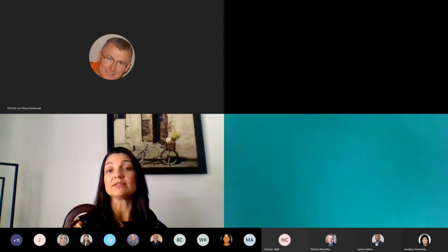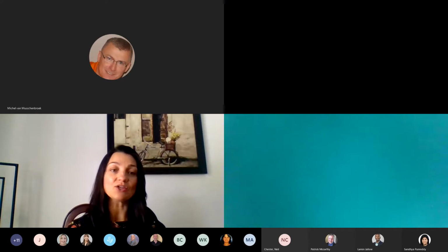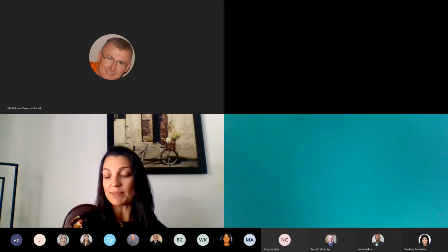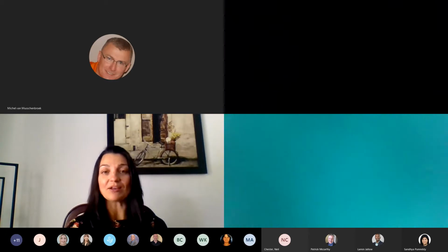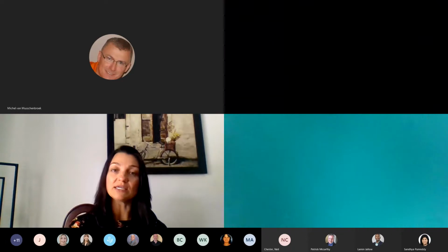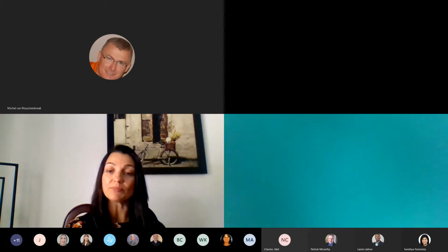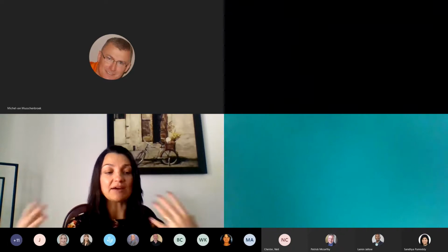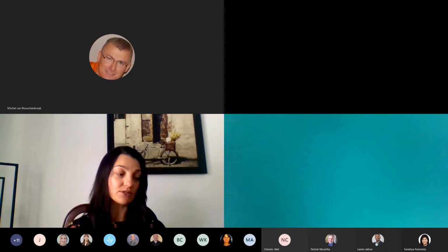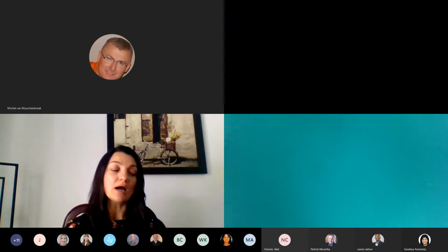So one thing is not the other, and you cannot have a validation if you don't have a qualification before that. So a bunch of qualifications, and they usually build upon each other. You can't have an installation qualification before the design qualification, and you can't have the operation qualification before the installation qualification. So it's usually a series of qualifications that one builds upon the other, and that forms your entire validation package. So that's very important to know.